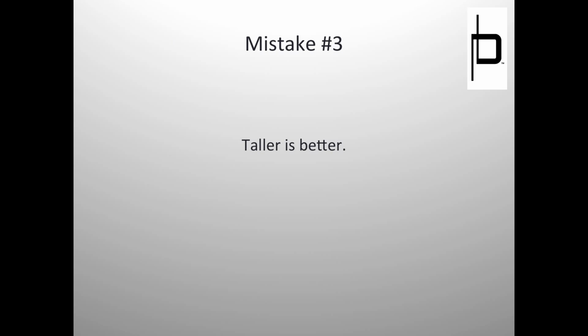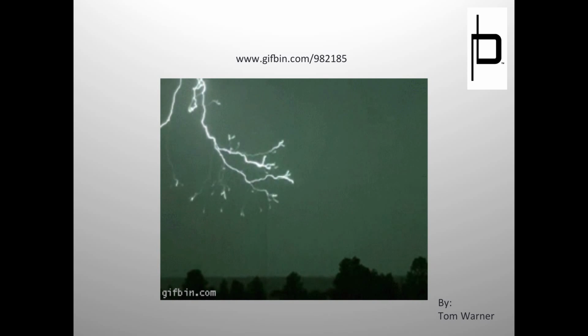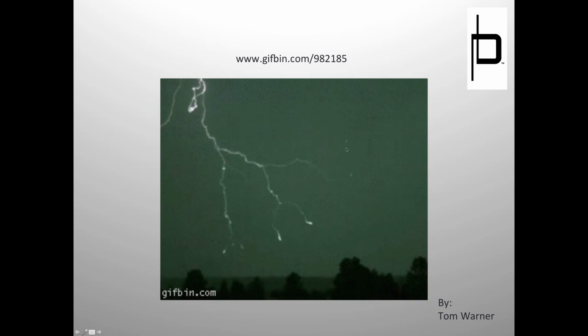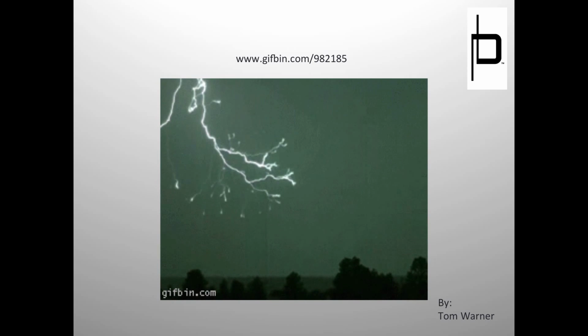Okay, so mistake number 3: taller is better. We talked briefly about this earlier. Remember, this video proves that step leaders can go sideways, can even come back up. You see some of these step leaders going up, certainly a lot going sideways. So we can't just assume top-down strikes for everything. That's not the right way to do this, to assume top-down strikes for everything.